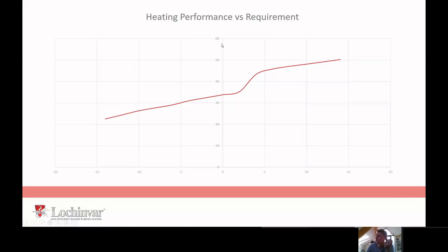Up through the middle, we've got the kilowatt rating of the electric air source heat pump. This is what I would call a 45 kilowatt air source heat pump, and it is 45 kilowatts when our outside air temperature is 7 degrees centigrade. Any time other than that, the kilowatt rating is different to the 45. But we would state it's 45 kilowatts because that's what the standard EN test figure, or European test figure for comparing products, is benchmarked on.